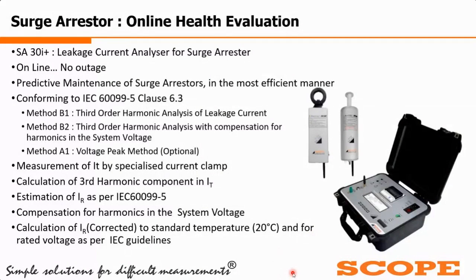This specific picture you can see is the SA30i+, which is the leakage current analyzer for surge arrestor. As we have told, we do not require any shutdown. It is an online kit. You can do the measurement directly in the online condition, so no outage is required. Preventive maintenance of surge arrestors can be done in the most efficient manner with this kit. It conforms to IEC 60099-5 clause 6.3, and there are three methods available inside the kit.